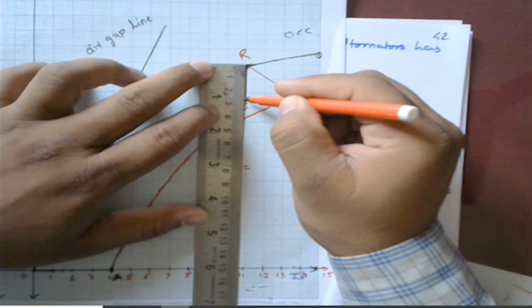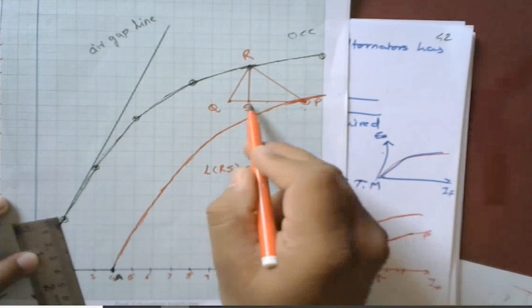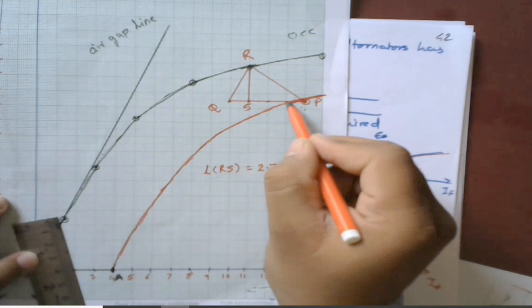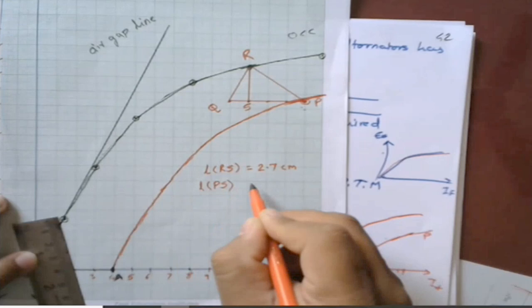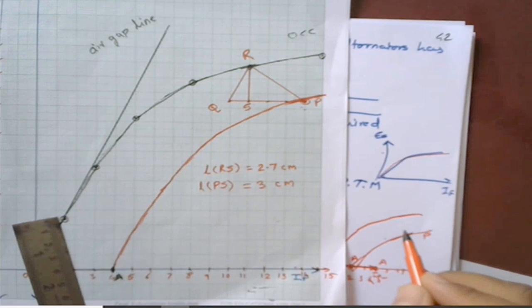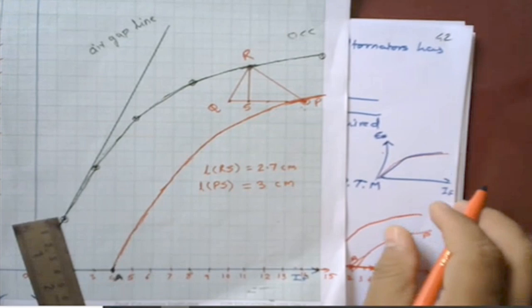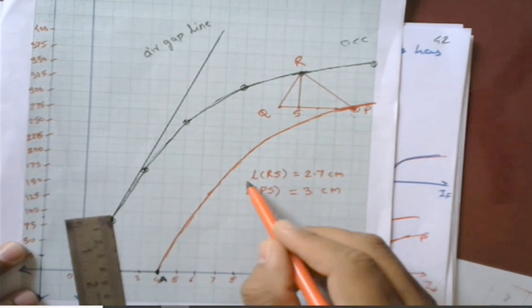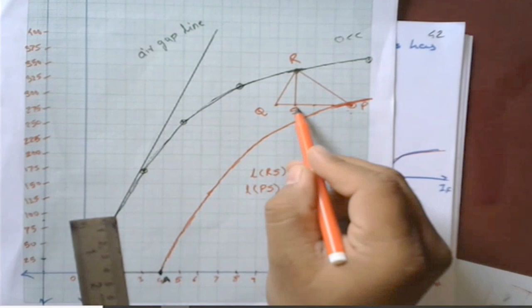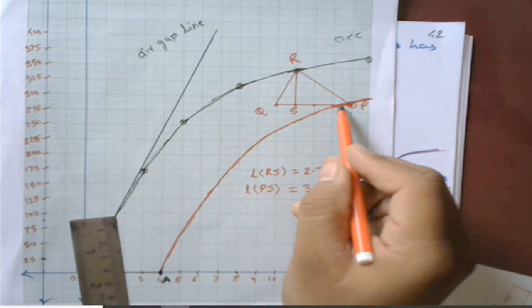Now measure the lengths: length of RS = 2.7 centimeter and length of SP = 3 centimeter. The length RS represents the leakage reactance drop (Ia × Xl), and SP represents the field current that overcomes the armature reaction effect (If2).